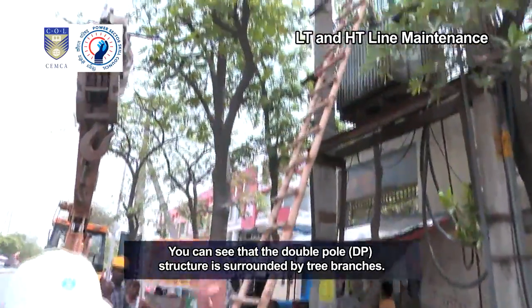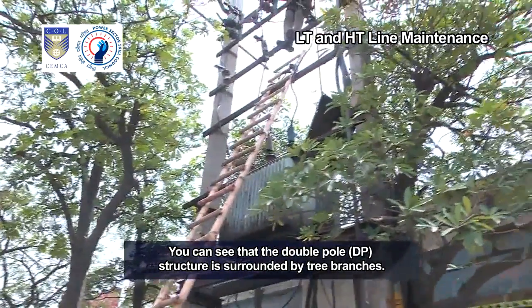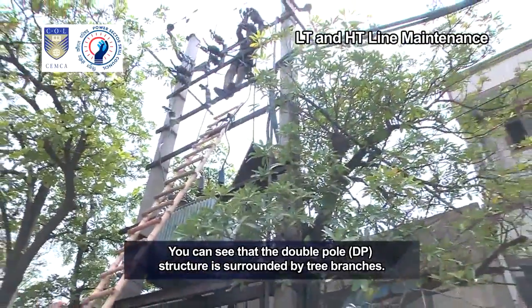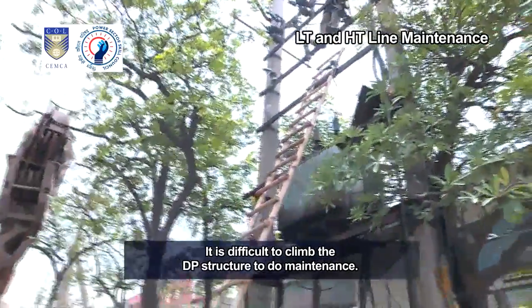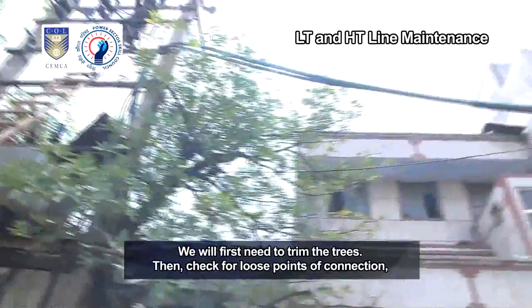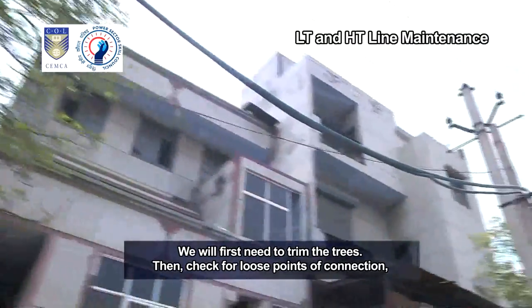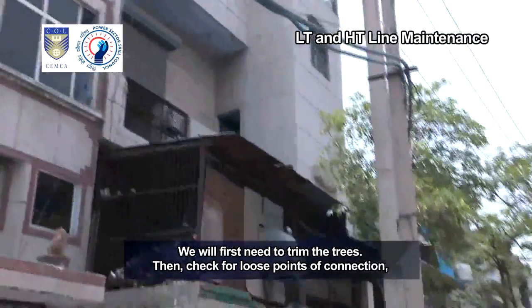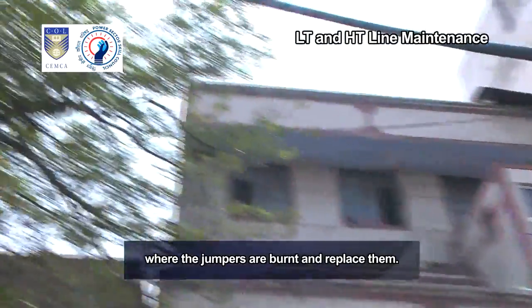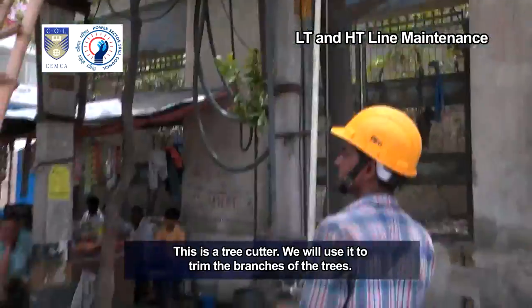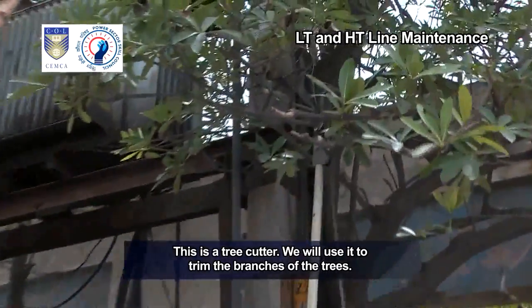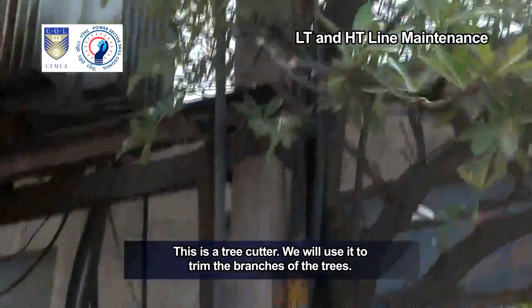You can see that the double pole DP structure is surrounded by tree branches. It is difficult to climb the DP structure to do maintenance. We will first need to trim the trees. Then check for loose points of connection, where the jumpers are burnt, and replace them. This is a tree cutter. We will use it to trim the branches of the trees.